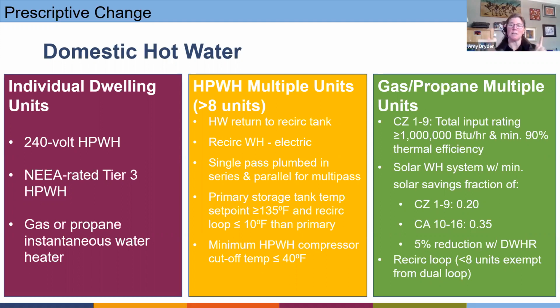A dual recirc loop means half the units are served by one recirc loop and the other half is served by the other. But if it's less than 8 units, you don't really need that. That dual recirc loop is to reduce losses over time. Okay.